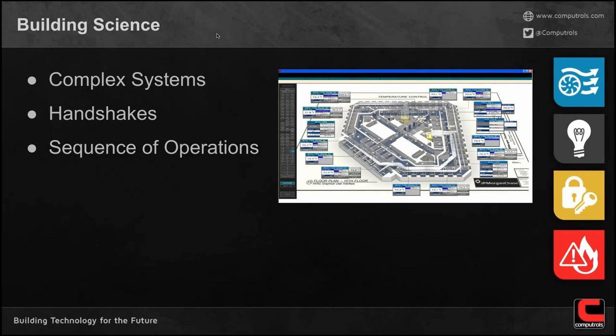Another use in the same application is that the HVAC system is often involved in a smoke evac situation. Again, every building has its own sequence and operation to follow during different events, and this is just one example. I'm only talking about a single smoke detector going into alarm. A single building may have thousands of smoke detectors, and essentially they could all generate a unique sequence of operations, though that's often not done this way.